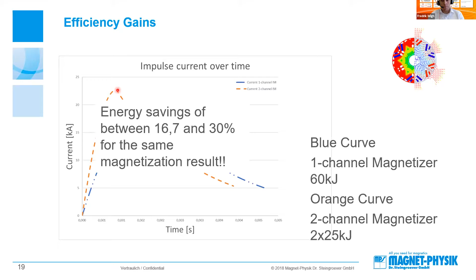To conclude, large traction machines can be magnetized in situ. The multi-channel approach can increase efficiency of the magnetization significantly. And there are two benefits of this. One is, of course, the saving of energy. And the second is it can be used to magnetize designs where a one-channel magnetizer would not be able to generate enough power or current. And last but not least, the use of the magnetizer is no different from a standard magnetizer. You can see a picture of a fixture here. The only thing is we need to connect 4 cables instead of the normal 2 cables to run the magnetization fixture. Thank you very much for your attention, and I leave the field open for questions.